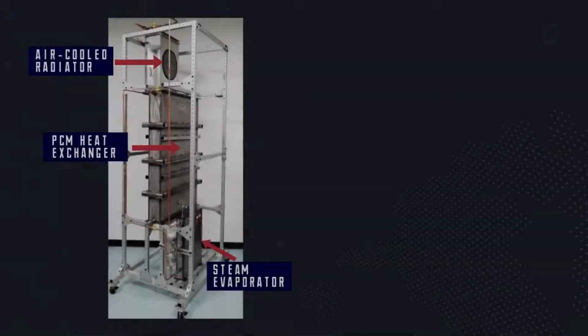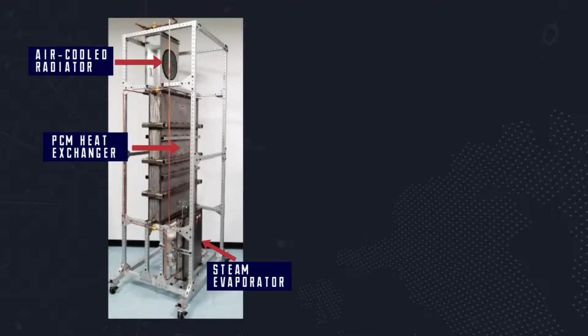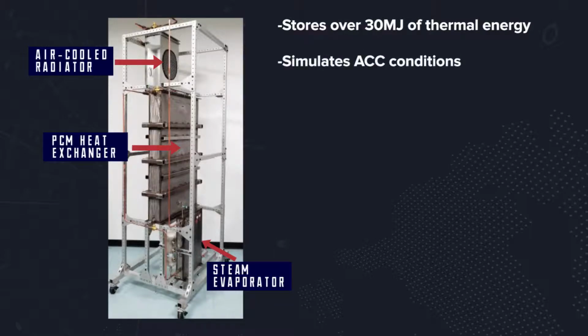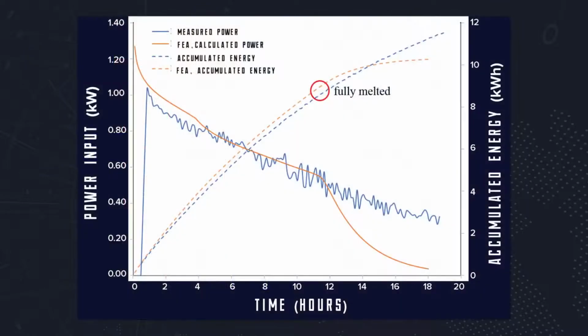At ACT, we designed and fabricated a prototype system that can store over 30 megajoules of thermal energy. A steam evaporator mimics the Rankine cycle to store heat in the PCM reservoir, while a typical air-cooled radiator removes heat, both via the loop thermosiphon system. The prototype, at optimized boundary conditions, melts in 11.5 hours. This experimental result matches within 10% of the finite element analysis modeling results.